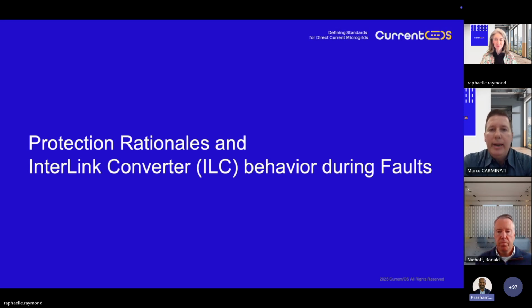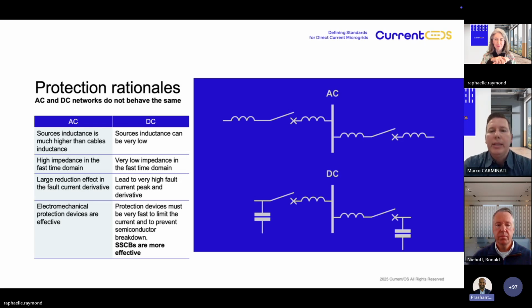So now let's talk about protection, rationale, and interlink converter behavior during faults. Here you can see the protection rationales, and in particular on the right you can see the conceptual single line diagram of both AC and DC low voltage distribution. If we start with the AC distribution, you can see that there are several inductances in series. Some of them are the inductances of the cables or busbar system, and the others are inductances of the local AC sources, like, for example, diesel genset, and the equivalent inductance of the AC utility.